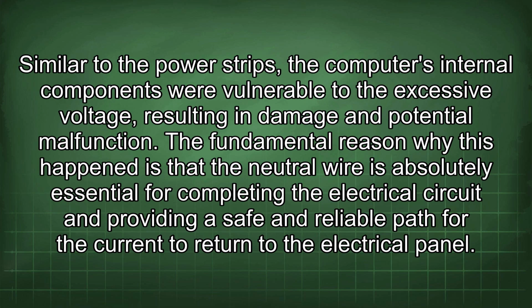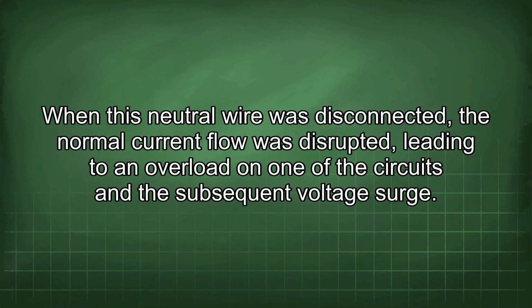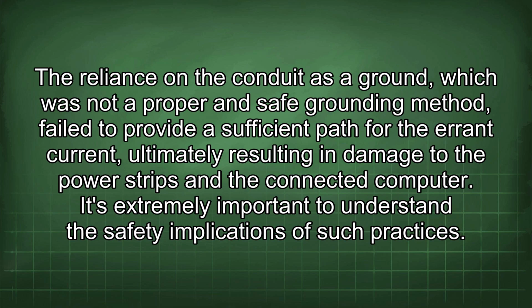The fundamental reason why this happened is that the neutral wire is absolutely essential for completing the electrical circuit and providing a safe and reliable path for the current to return to the electrical panel. When this neutral wire was disconnected, the normal current flow was disrupted, leading to an overload on one of the circuits and the subsequent voltage surge. The reliance on the conduit as a ground, which was not a proper and safe grounding method, failed to provide a sufficient path for the errant current, ultimately resulting in damage to the power strips and the connected computer.